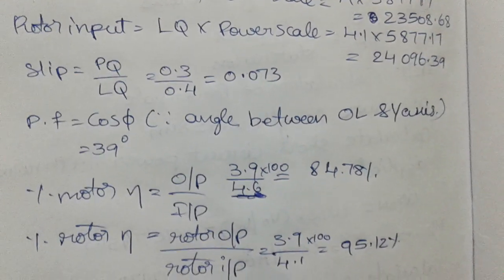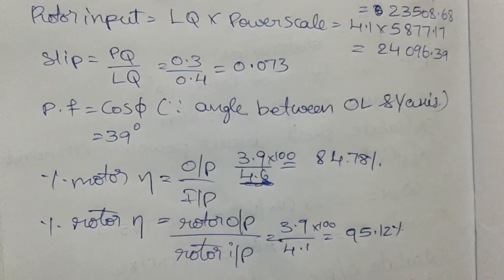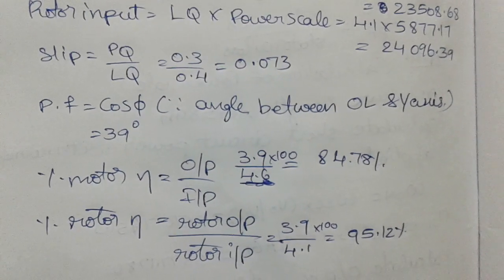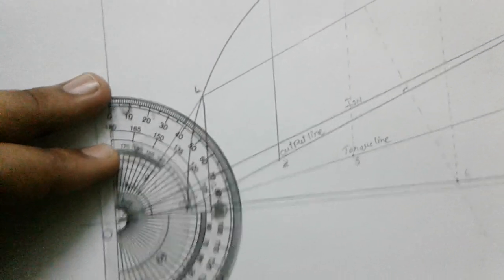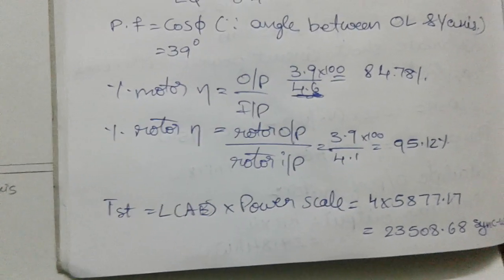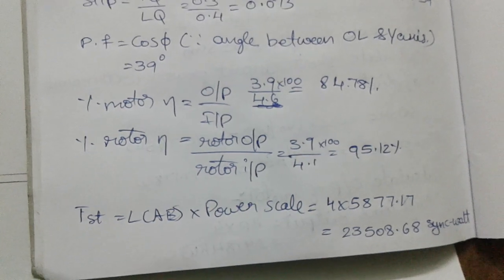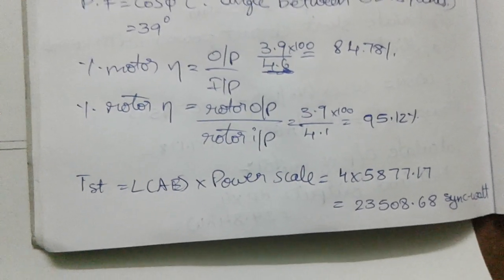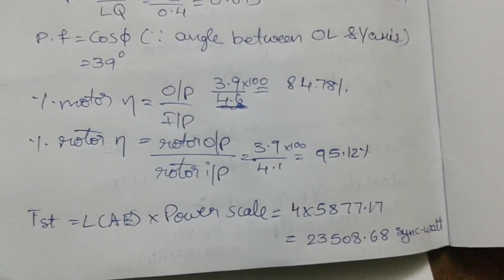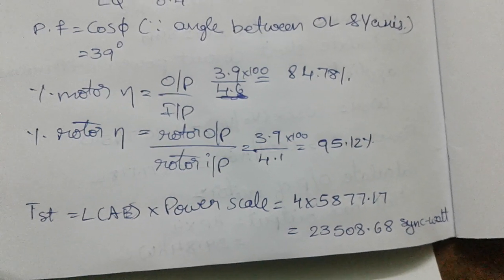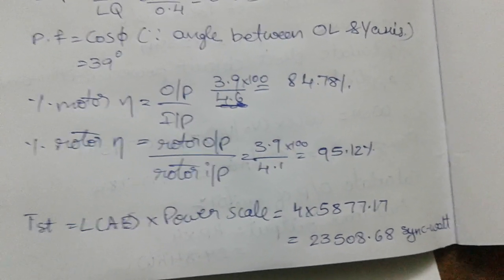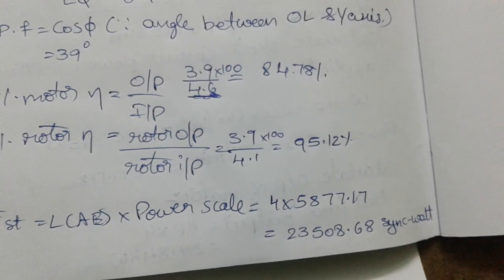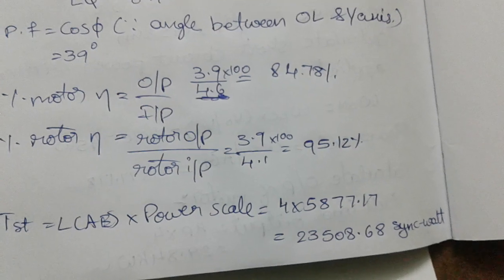The power factor, cos φ, is the angle between OL and the Y-axis, which is 39 degrees, measured from the circle diagram. Motor efficiency equals output divided by input: 3.9 divided by 4.6 multiplied by 100, giving 84.78 percent. Rotor efficiency equals rotor output divided by rotor input: 3.9 divided by 4.1 multiplied by 100, giving 95.12 percent.